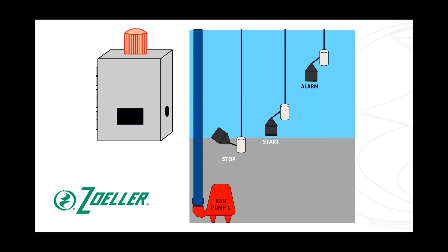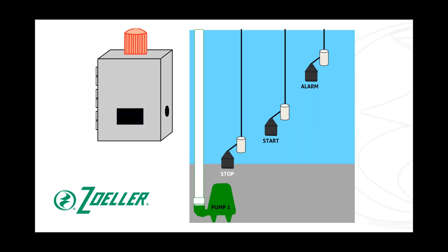So now water is going down. You can see our alarm float dropped out. And when our alarm float dropped out, our audible and visible indicators were shut off. And the pump stays running and it's going to continue to pump down the water. Again, you can see here now our start float has dropped back out. The pump is still running. And lastly, now the stop float has dropped out and we have completed our pumping cycle. This control panel, it's shut off. It's ready for the next cycle.